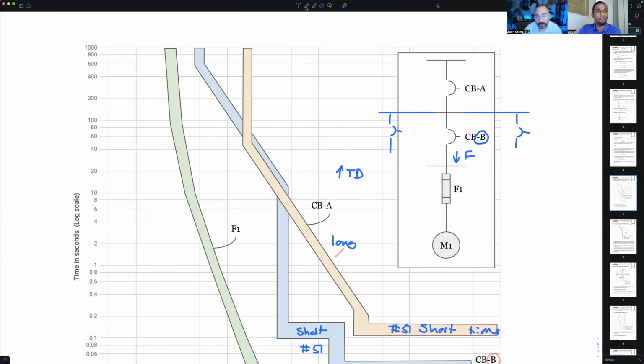I'll use a different color besides blue, since blue is too close to circuit breaker B—I think orange is better. So this is what increasing the time delay would look like. I'm tracing the curve, and as you said, increasing the time delay shifts it up on the vertical axis. If I moved this up like that, here's what our new curve would look like.